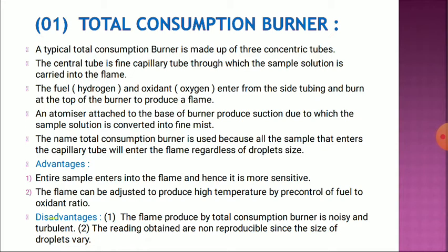Now the disadvantage. One, the flame produced by the total consumption burner is noisy. That means when the flame is produced, it creates noise. That's why this burner has a noisy and turbulent flame.